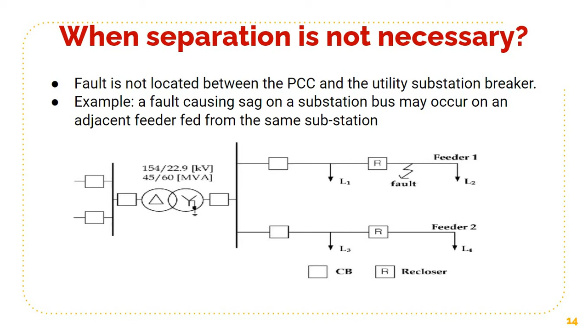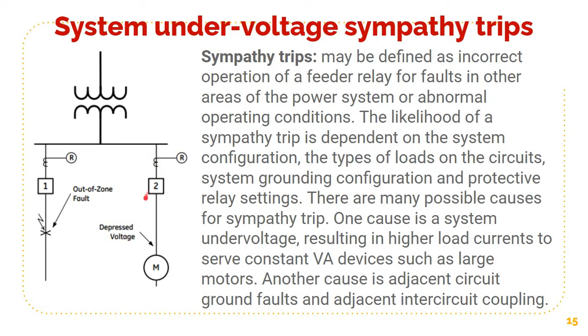Such types of trips are called sympathy trips. A fault occurring in one feeder reduces voltage in another feeder, and that is picked up by this particular relay, tripping the second feeder. So this is called a sympathy trip.